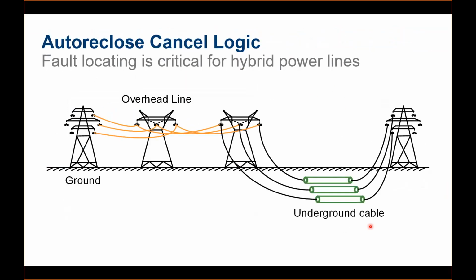All right. One more application that we can get out of these modern technologies is auto reclose control, or auto reclose cancel logic. In some hybrid applications where we have overhead line and some underground part, or maybe more sections of overhead and underground, there is always a challenge to block the auto recloser for the portions of underground cable. Or maybe there's a tap-off line somewhere, so you don't want to auto reclose in that location. This is a challenge for conventional distance protection, and either you will block it, or you will compromise on selectivity. So we have auto reclose cancel logic, where the relay can pinpoint or block the auto recloser in that region where you want it to be blocked.